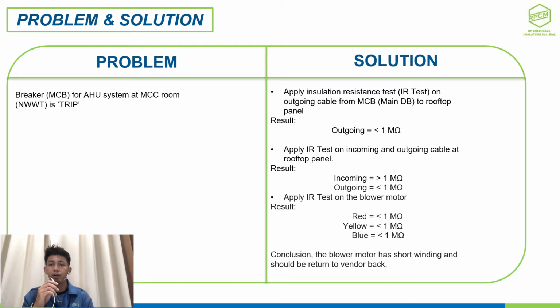Then the result for the IR test for the outgoing cable is below 1 mega ohm. So after that, we went to the rooftop panel to check whether the short comes from the main breaker or the motor. After we checked, we got the result, which is the incoming cable is more than 1 mega ohm, while the outgoing cable is below 1 mega ohm. So we concluded that the short comes from the motor.